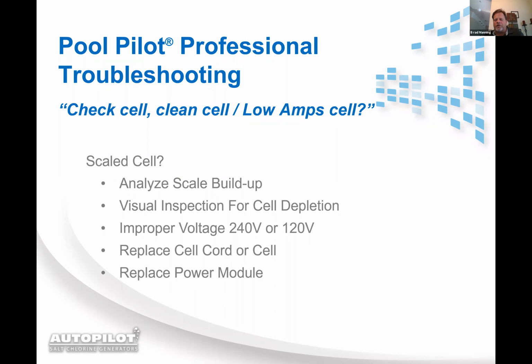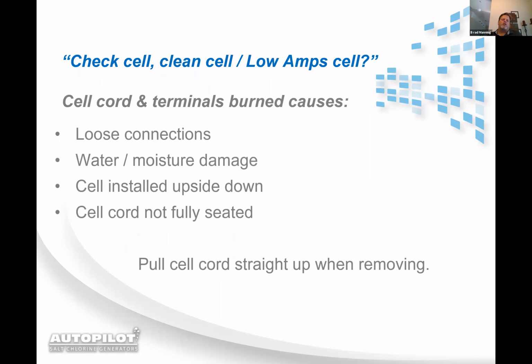You want to inspect the cell for corrosion, or the cell cord for corrosion where it plugs down onto the cell, or look up at the terminal strip, see if you have corrosion there or any burn marks. How do cell cords burn up? Loose connections for one, moisture inside the cell cord itself. A lot of times when cells are cleaned, they get cleaned and then water gets left on the post, and then you plug the cell cord back down onto that post with water and moisture there. It's going to corrode the copper brass connections inside the cell cord.